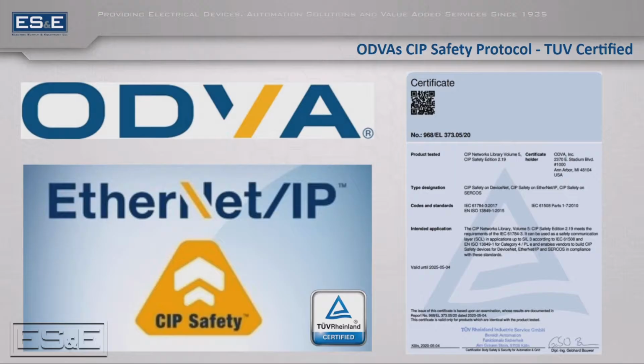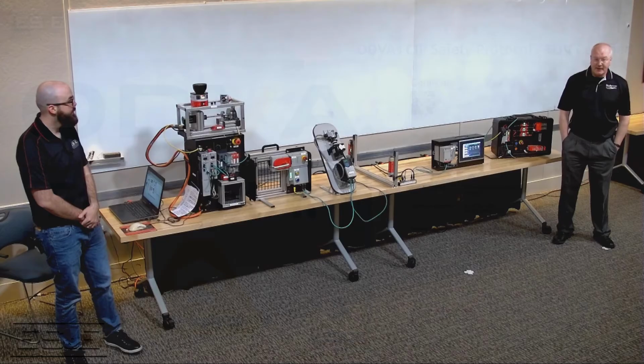There was a question in the chat saying, with a very bad network, could the error detection cause artificial stops? Actually, yeah. But the real question is, should you have a good network in the first place? If you're doing CIP safety or non-CIP safety, just for regular standard Ethernet I/O, you should have a solid network. Even without safety, you've got to have it, else your I/O will drop out and your machine will stop. But yes, there is the possibility of stopping your machine on a bad network, and that's just indicative of having a bad network. So first priority is get your network nice and solid.